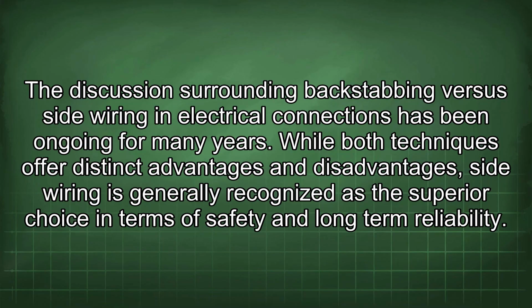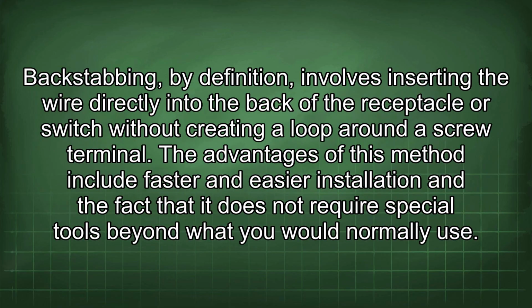The discussion surrounding backstabbing versus side wiring in electrical connections has been ongoing for many years. While both techniques offer distinct advantages and disadvantages, side wiring is generally recognized as the superior choice in terms of safety and long-term reliability. Backstabbing, by definition, involves inserting the wire directly into the back of the receptacle or switch without creating a loop around a screw terminal. The advantages of this method include faster and easier installation and the fact that it does not require special tools beyond what you would normally use.